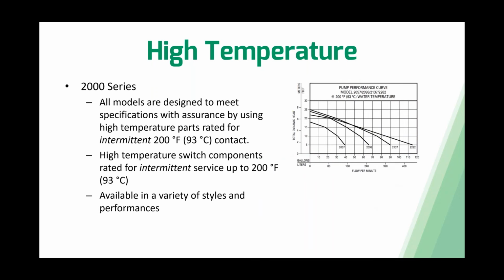Within the high temperature pumps, we have a couple different series. We have our 2000 series and our 3000 series. On the screen now, you will see our 2000 series, so we'll start there. All models within the 2000 series are designed to meet the specifications with assurance by using high temperature parts that are rated for intermittent 200-degree contact. Also, the high temperature switch components are rated for intermittent service up to 200 degrees. You'll see I have intermittent italicized there. That's very important to pay attention to when it comes to the 2000 series versus the 3000 series.